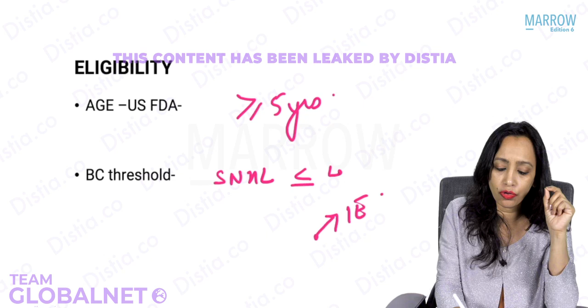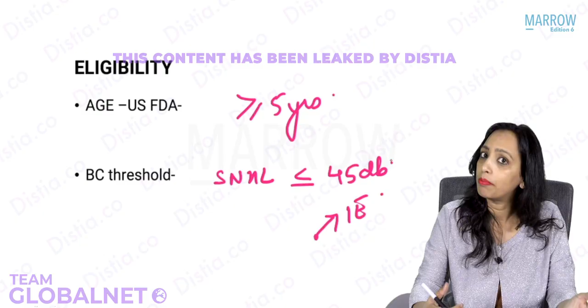Yes, so the sensorineural hearing loss should not be more than 45 decibel. It should be less than or equal to 45 decibel. Even if you're stimulating the other ear, the other inner ear should be good. Only then is there a role of putting this Baha. In patients in whom the external ear is well developed, if there is a conductive hearing loss or a sensorineural hearing loss which is not severe and profound, the hearing aids work well. The hearing aids do not give a gain of more than 80 to 90 decibels.